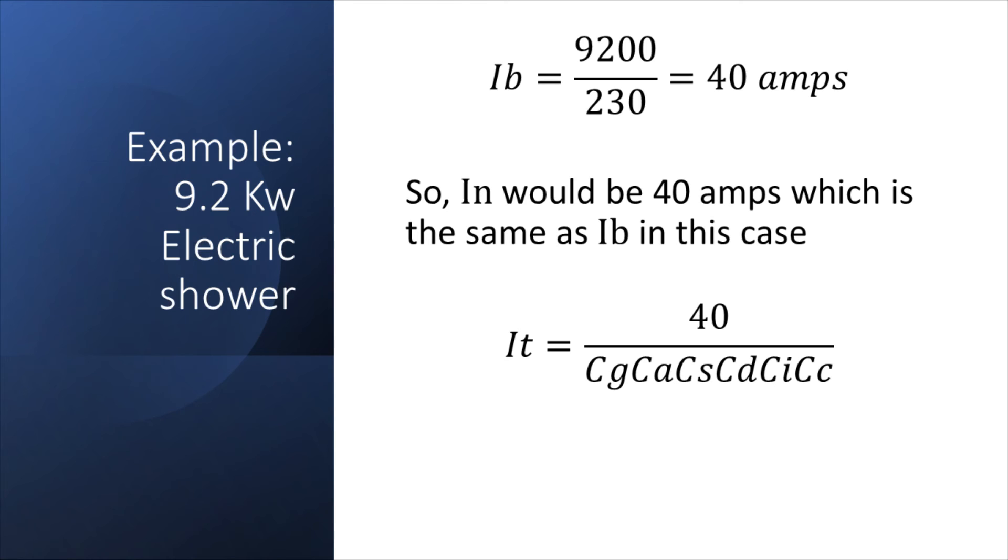In this first example, I've done a calculation for a 9.2 kilowatt electric shower. So the design current IB, we've got 9200 divided by 230, which gives us 40 amps. In this situation the IN would be 40 amps, which is the same as the IB. So in this case the calculation is the same. The value for IT would be equal to 40 divided by any applicable correction factors, and that would give us our IZ.